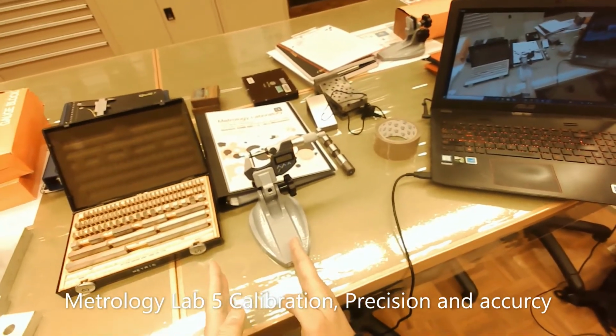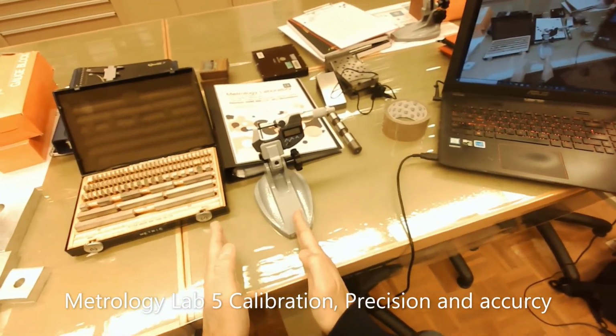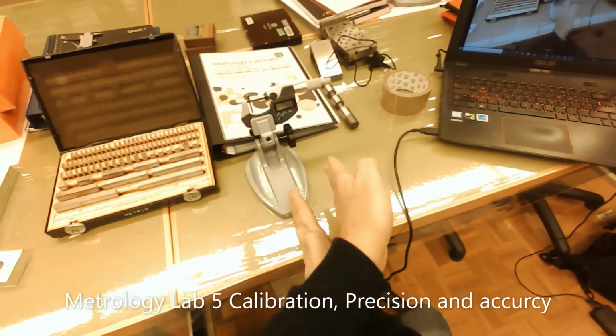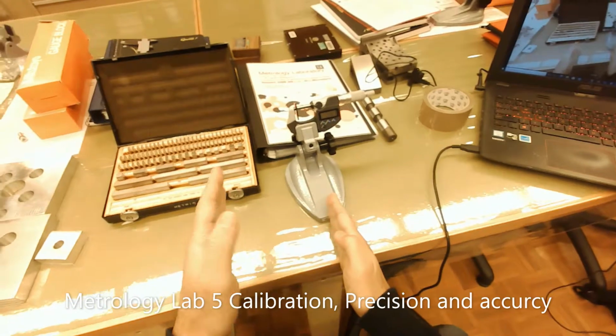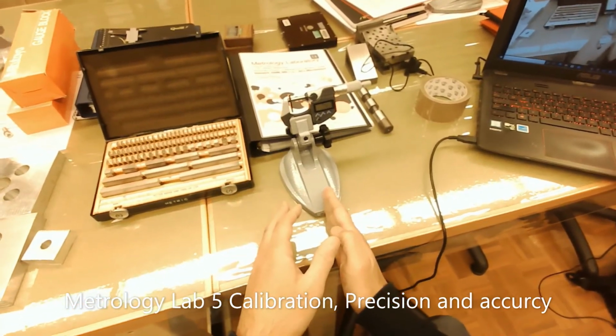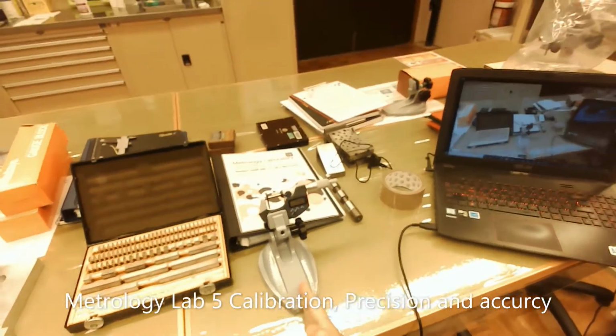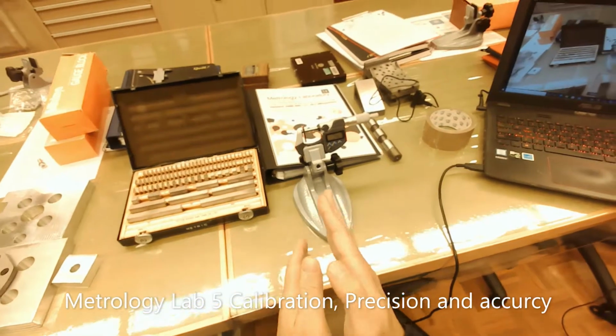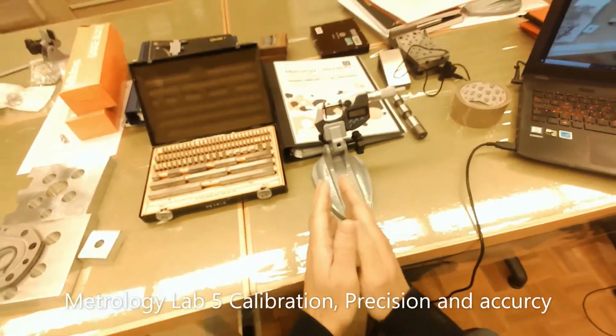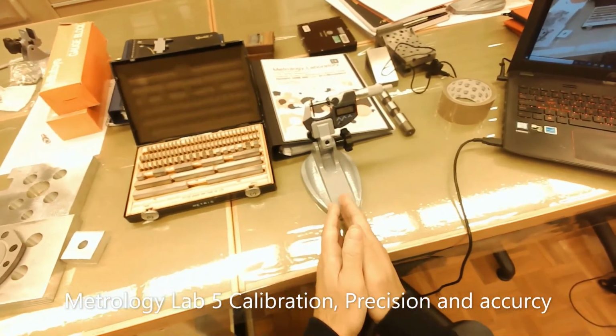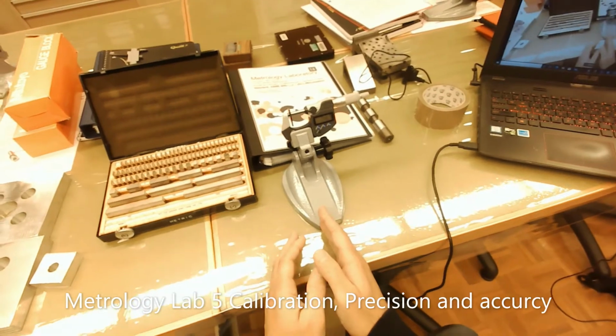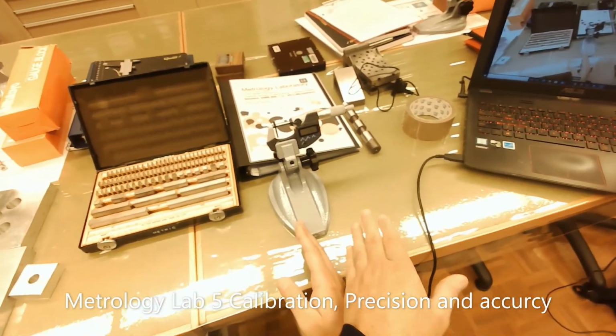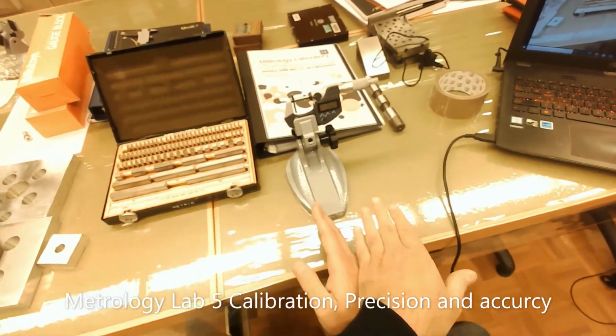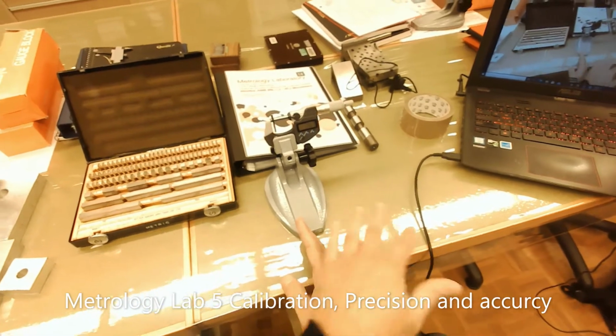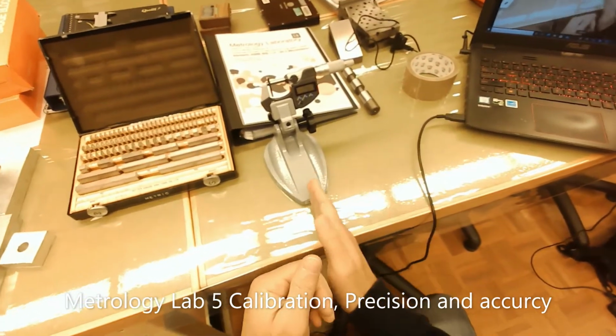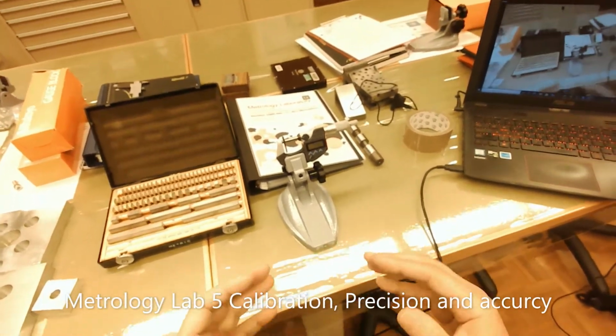Now what will be the reading in the next situation? If this is the mean value, my readings are going to be one here, one there, one here, one here, and one there. That means my device has bad accuracy and bad precision at the same time. So precision is the repeatability of the readings close to and within the mean value. This will be good precision and good accuracy. If my readings are within the same range but away from the actual value, this will be bad accuracy but good precision. If my readings are distributed variably along the mean value, that means it has bad accuracy and bad precision at the same time.